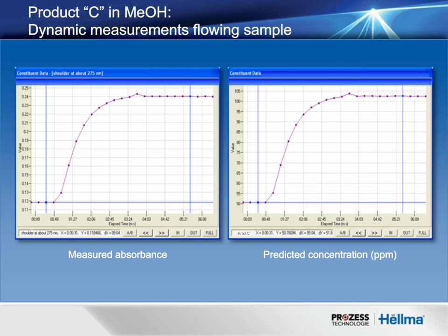Have you gotten any regulatory approval of your UV-Vis cleaning method? Our systems definitely are 21 CFR compliant, GMP compliant. But typically the cleaning method itself is done by the end customers. It's up to their particular protocols to correlate the direct UV approach with their existing approaches. That is typically a multi-step process of using the two in tandem to show correlation before ultimately relying on an inline approach. And again, that would be up to the customer.